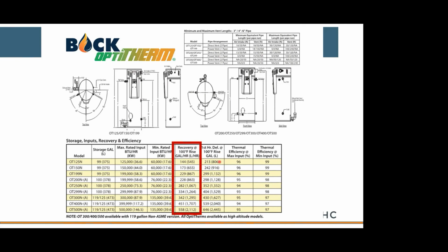This first hour delivery, this is where you need to be a little bit careful. It's taking advantage of the storage that's in your water heater. Now you can't use all 99 or 100 gallons of it, but you could use roughly 70 gallons of it before water cools off enough, and now you're relying solely on your burner recovery. So most of the time you're selecting your tank type based on recovery alone, not first hour delivery. I hope that makes some sense.